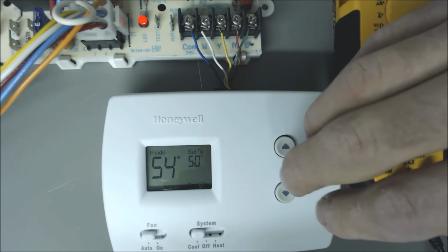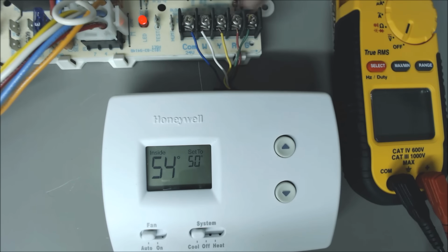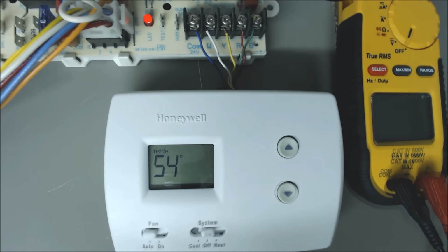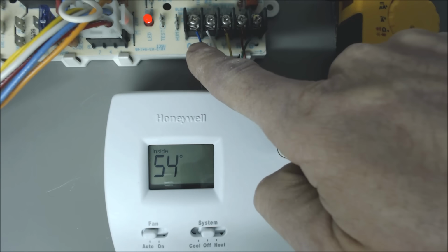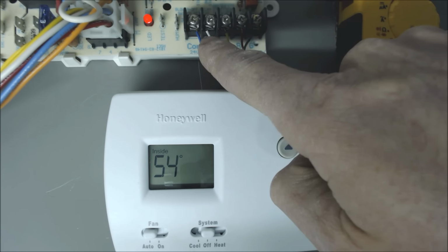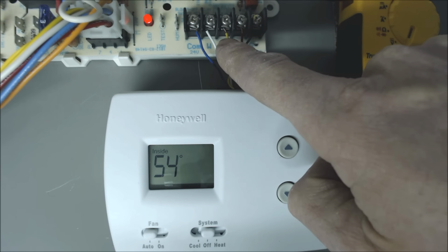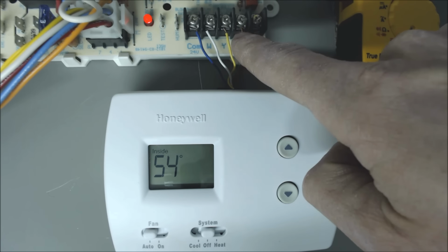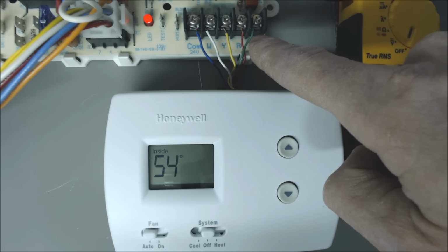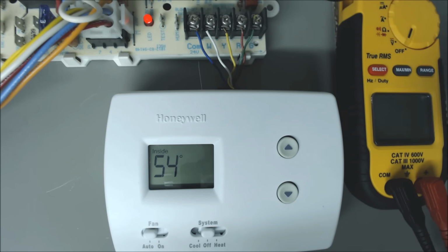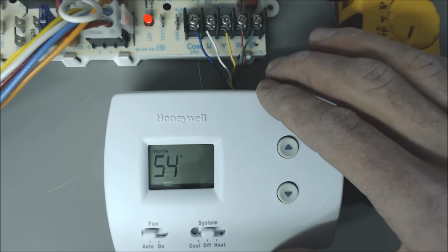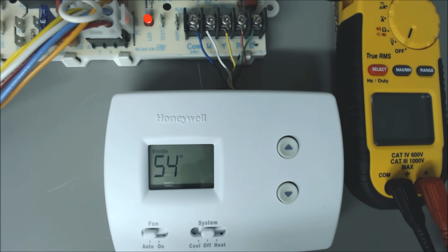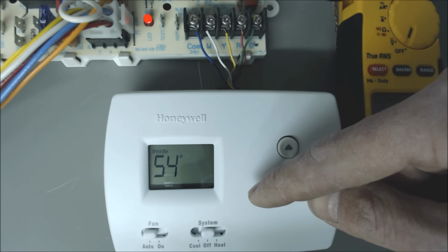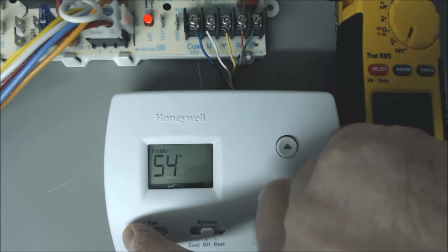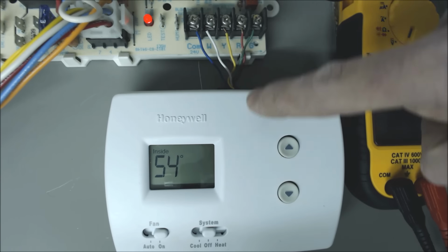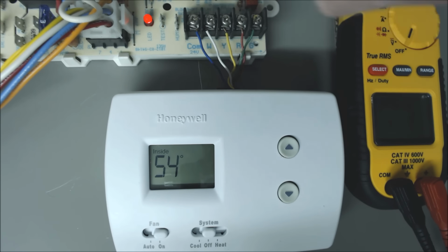So this is all to test your thermostat and your thermostat wire out, and we're going to read our voltages right on the terminal block of our control board. To start off, our common wire is C right here, our heat wire is W, our cooling wire is Y, our power wire is R, 24 volt power, and our G wire right here, that is for fan. All of those are wired right into the thermostat, and we just want to make sure that our R voltage comes to the thermostat, connects to, say, G, we're turning the fan on, and then it comes back to the G terminal on the control board of the furnace.